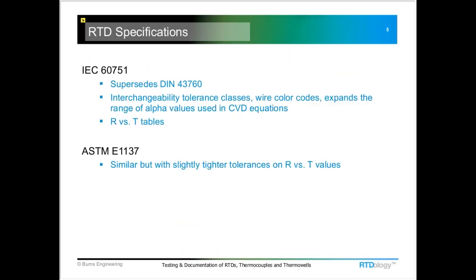A couple of standards define the resistance versus temperature relationship. The international standard is the IEC 60751. Previous to that, it was DIN 43760. What these standards do is look at this resistance versus temperature relationship, and then assign what we call an interchangeability or a tolerance class to that relationship. In the U.S., there's an ASTM standard. It does the same thing with slightly tighter tolerances.